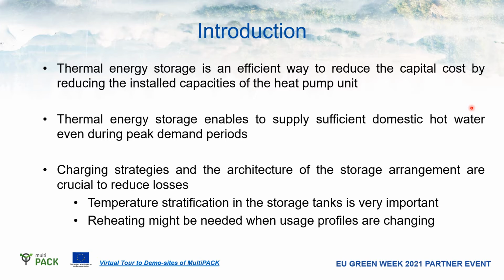And what is very important is to understand how to charge these kinds of thermal storage devices and the architecture, how to build up this infrastructure. In this respect, the thermal stratification in the storage tanks is very important, because the heat pumps are much more energy efficient if the return temperature is as low as possible. In some cases, reheating of the already stored water is needed, and I will show you some potential strategies to do that.